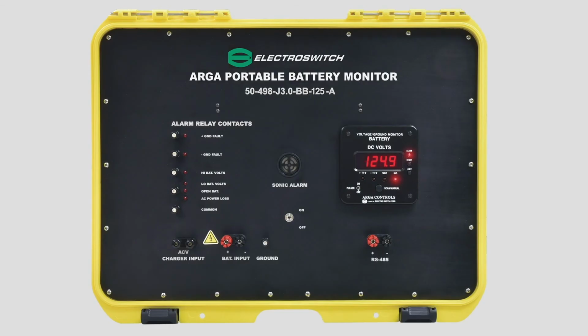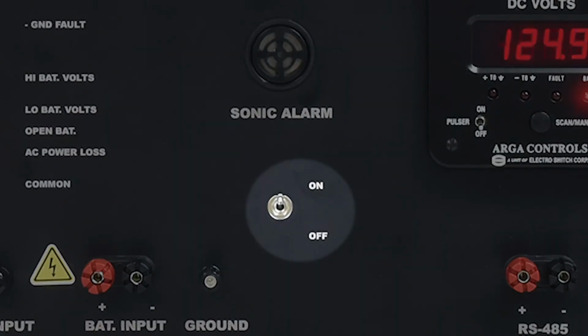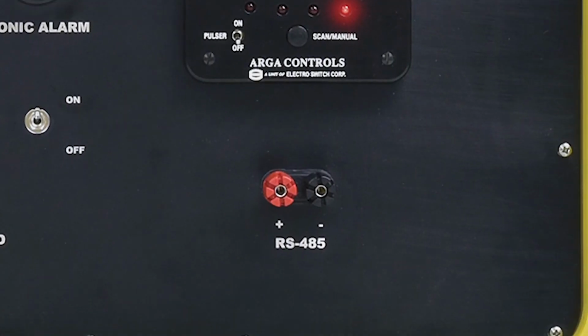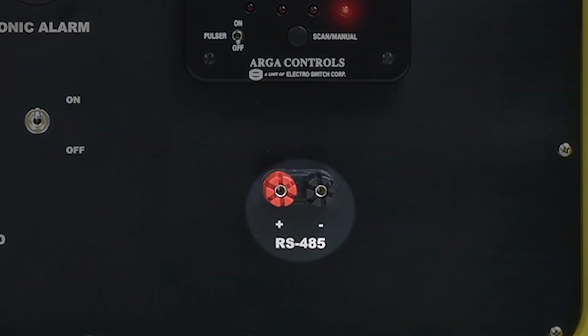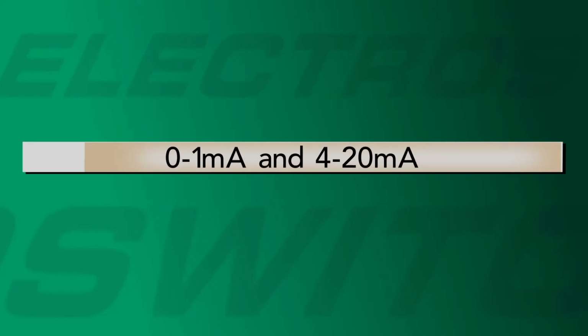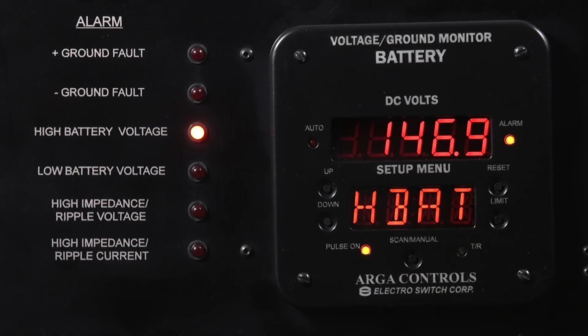It is a little different on the portable unit, as there is a toggle switch to turn off the audible alarm. If this was hooked up to serial communications using DNP 3.0 or Modbus, you would be able to send output alarms and voltage to the SCADA system. As an alternative, output options include current source outputs of 0 to 1 milliamps or 4 to 20 milliamps by direct connection. As the voltage is again decreased below the 142 volt DC set point, the LED alarm on the meter will go off, and then the other high voltage alarm LED on the monitor case will go off.